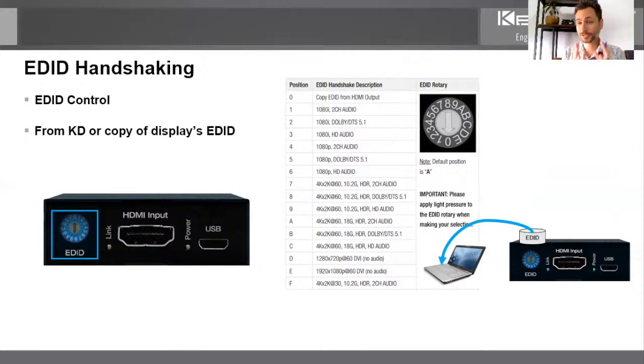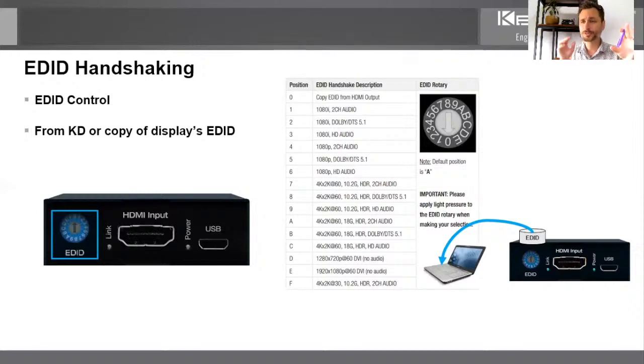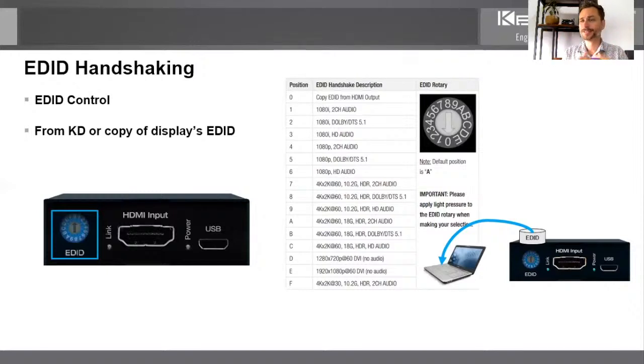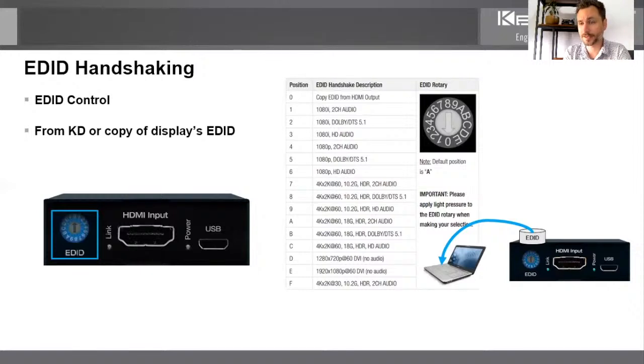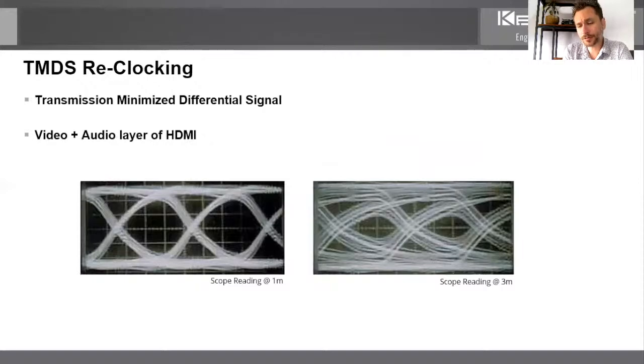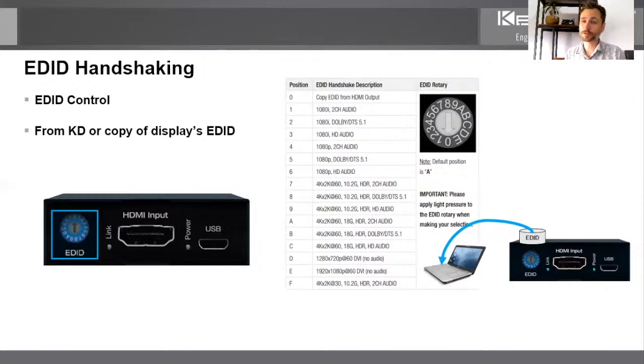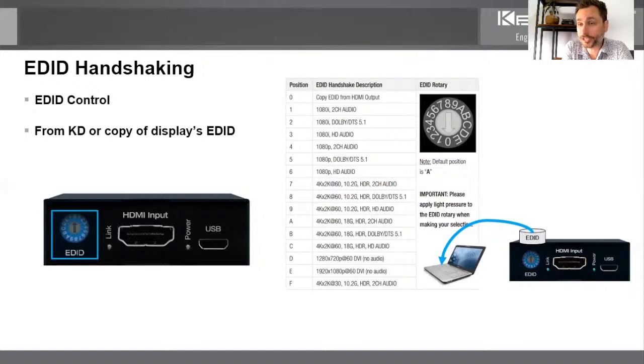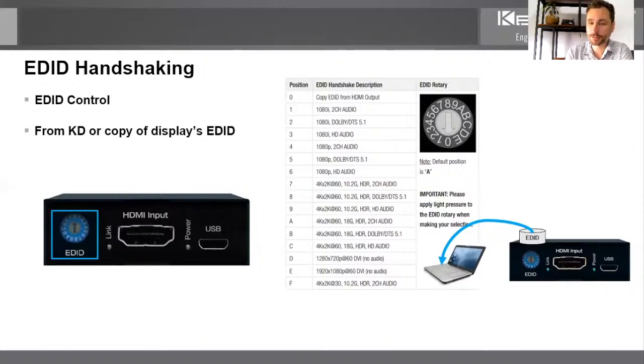In addition to that though, you have 15 other EDID handshake options from 1080i with three audio formats to 1080p, 4K at 10G, 4K at 18G, and a number of DVI handshakes in case that is what you're looking for. And so this is going to be a problem solver. You might say, I don't know why there's an issue. I got a brand new 4K source, a brand new 4K display, but you know, they're not seeing eye to eye. We have 15 different options in here. One of them is going to save the day for you. And I should note also that this EDID library, starting to see a lot of changes now in the various key digital products. And so why is it changing? Because the formats and the resolutions are improving. And so we're constantly evolving with the technology.